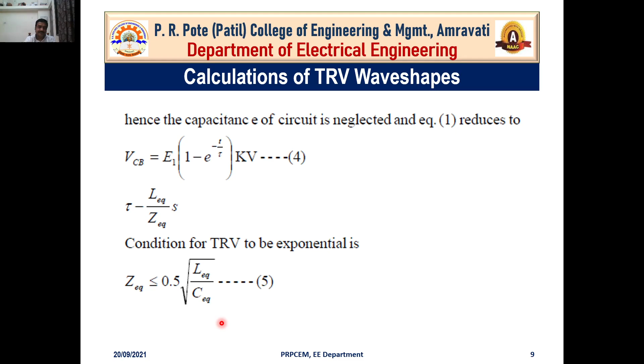Now the third one is the triangular or sawtooth type of TRV. You will obtain this TRV when a fault at a shorter distance from the circuit breaker on the transmission line is interrupted. It results in a triangular TRV on the line side of the circuit breaker, characterized by a high rate of rise of recovery voltage. So usually this sawtooth TRV is observed when we interrupt the fault current where the circuit breaker is connected at a very short distance from the fault.